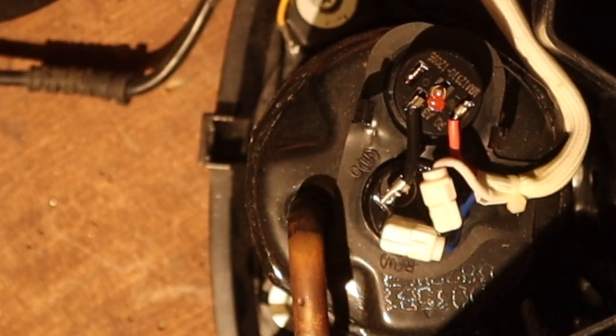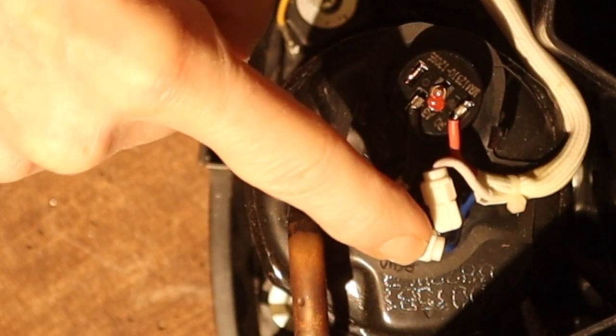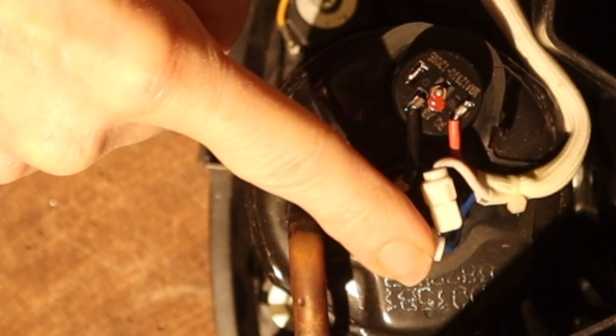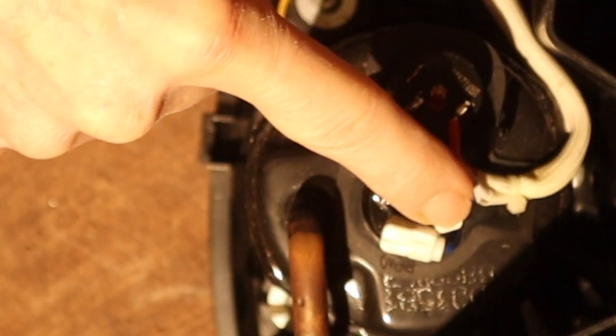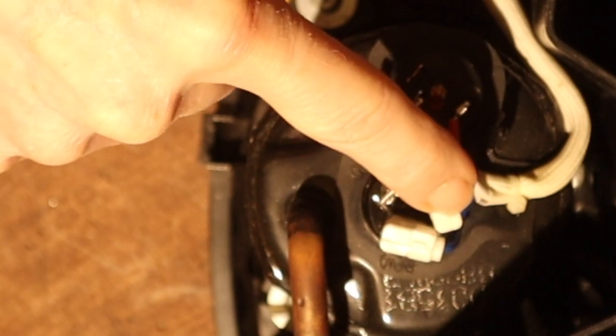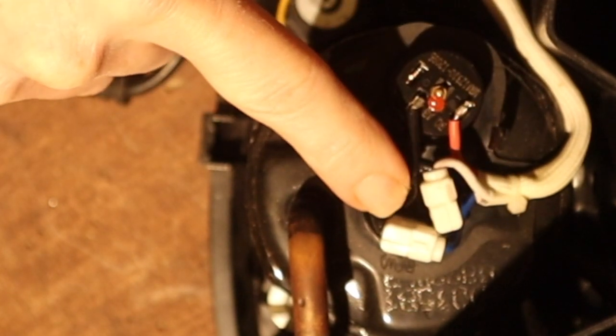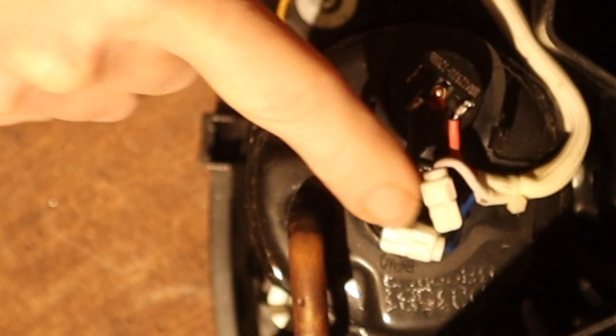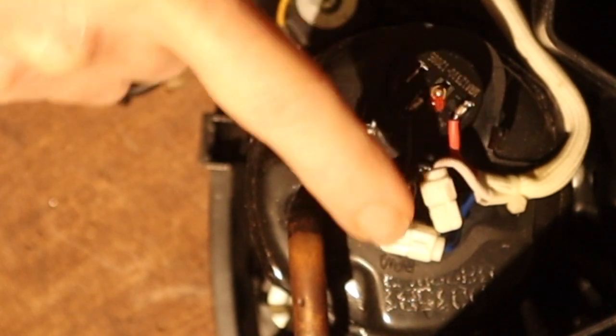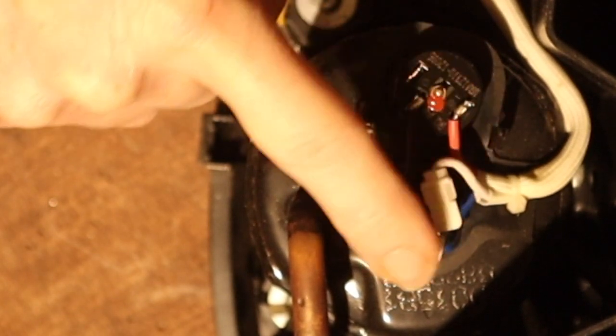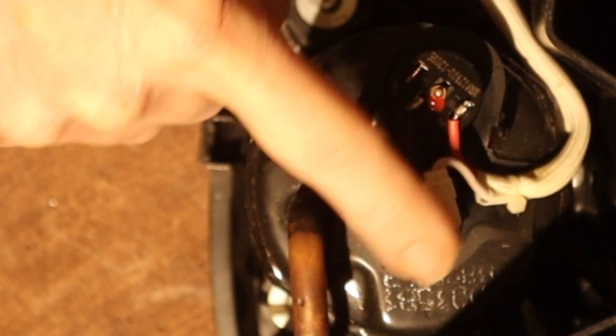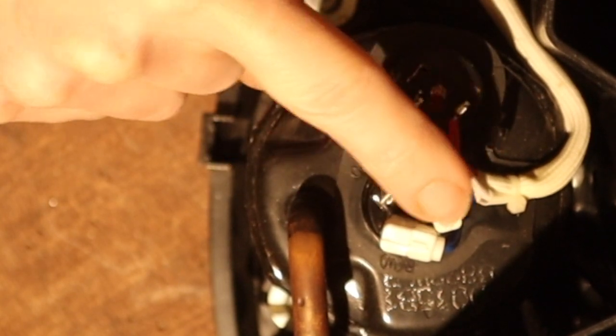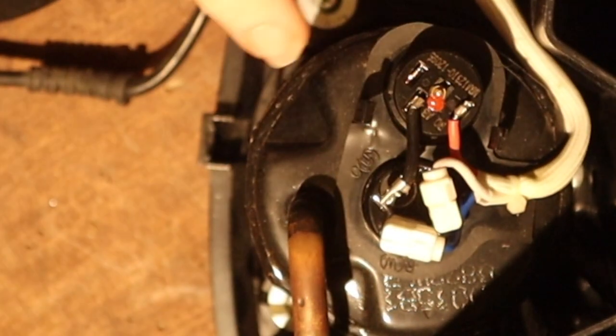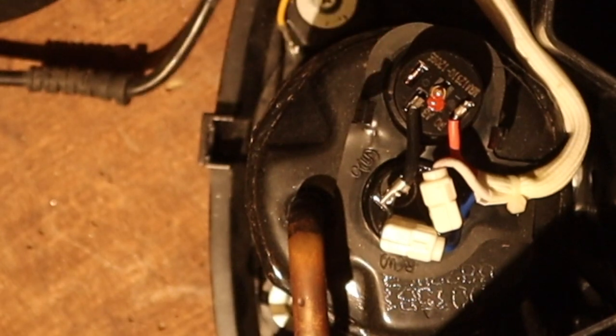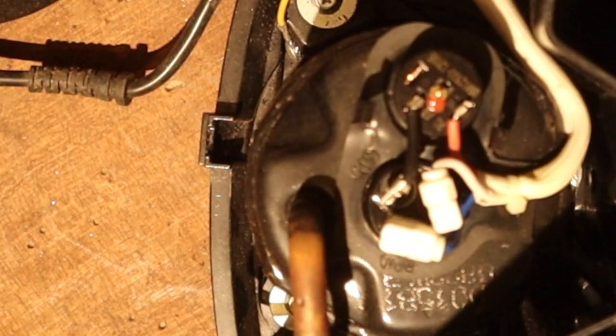And you know that this capacitor has one pole which is for himself. This can only be the shared contact, because this also goes to this. This here is also a winding, so here is one winding and here is one winding. This is the start winding, and this is the running winding. And you can also check that with the ohm meter.